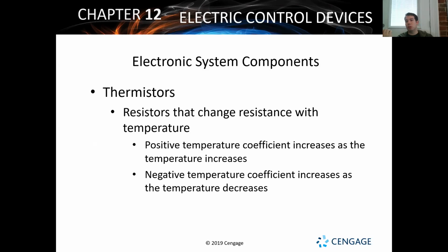These thermistors will actually be connected with zone control dampers, to open and close airflow and allow heat to flow out where it needs to go. So there are a lot of different applications for them, but one of the big ones is zone controlled systems, which will use a thermistor as a temperature sensor for the room. That way, the only thing that really sets the temperature for the house is the thermostat, and the thermistors make it so the system maintains that temperature in every room.